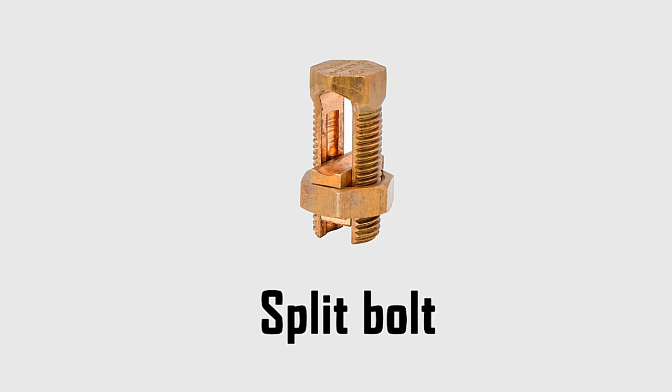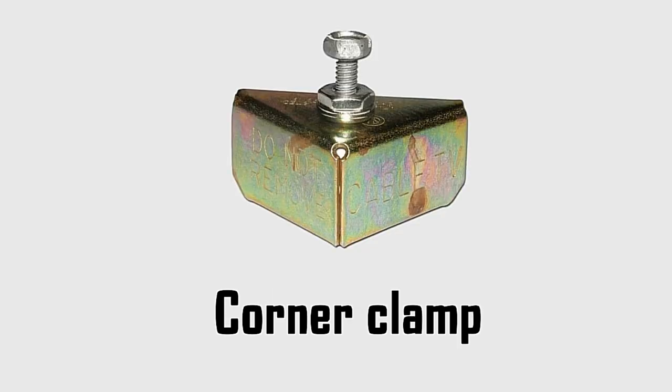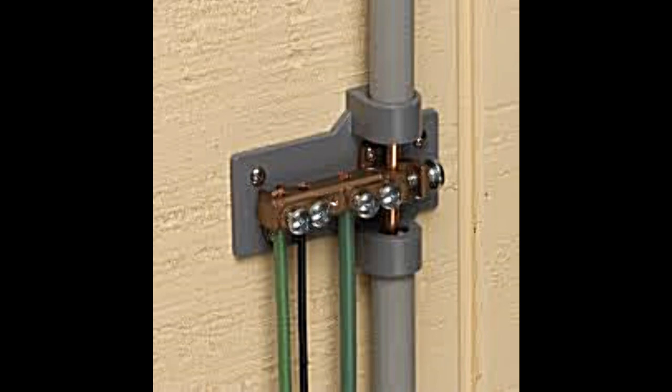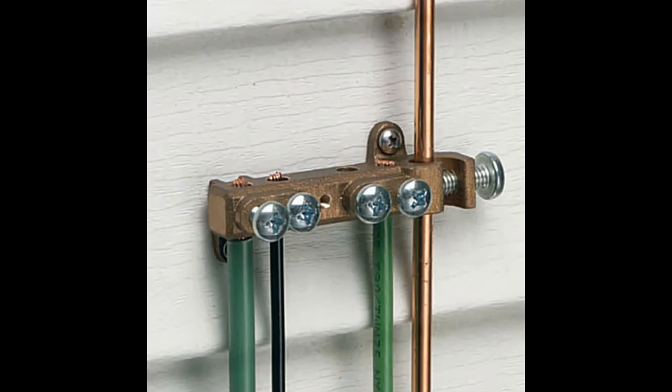You can use what we call the split bolt, a corner clamp for your meter box. But the best way to do this is to use what we call the inter-system bonding connector. Now what it is, it's a grounding connector with multiple ports. So if ever in the future you decide to install any extra antennas, you're going to have the extra ports readily available, without having to add another grounding lug or split bolt or anything like that.